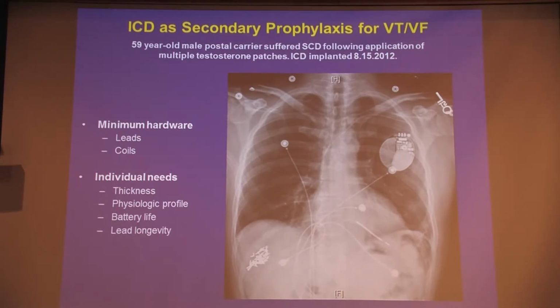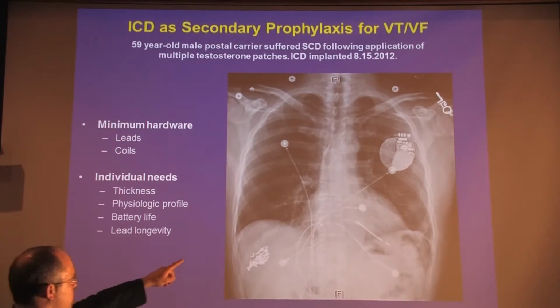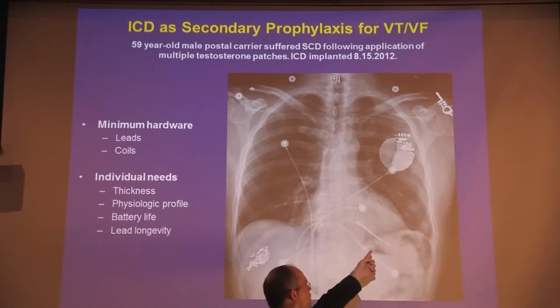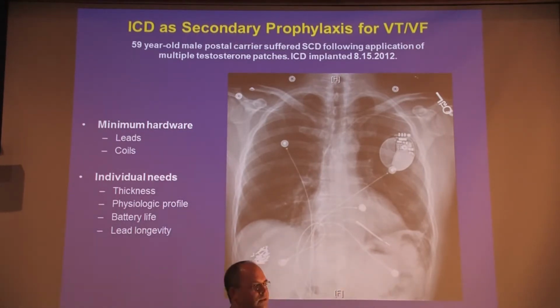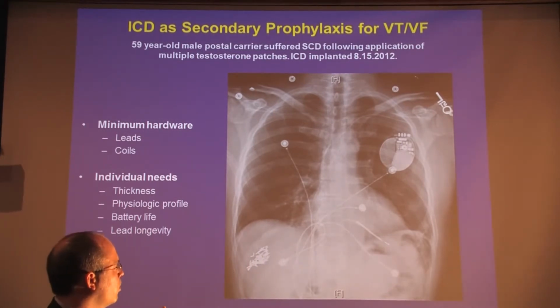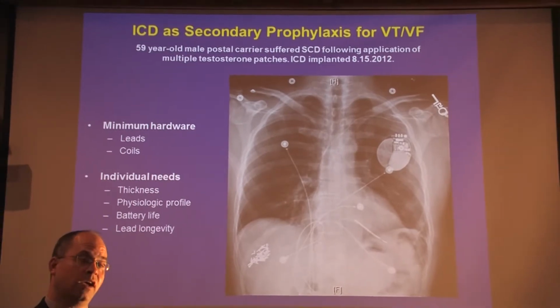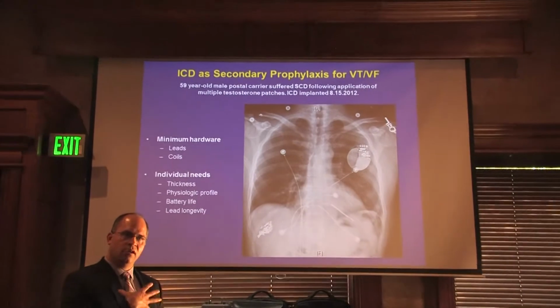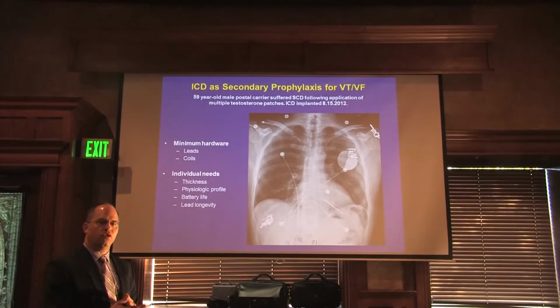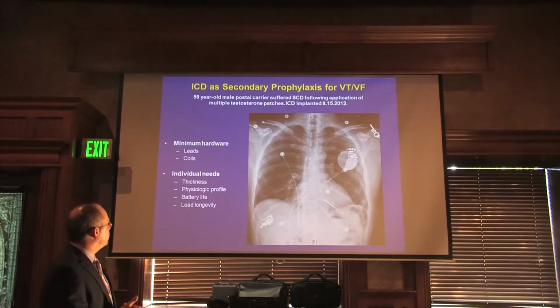We brought him into the hospital, shocked him a number of times to finally settle him down. And then as a part of the discharge process, you need an implantable defibrillator to protect you from this happening again. So what we see is it looks very much like a pacemaker, only it's bigger, more battery power. And the lead, here we see a single lead passing into the ventricle, and that thick coil on the end of the lead that you didn't see on the pacemaker, that's the shocking coil. So should that device detect a rhythm, that device can charge up, and between that coil and the device itself deliver a vector of shock energy able to reset your rhythm to normal. And that's the basic function of an ICD.